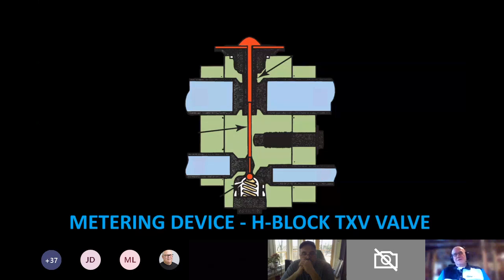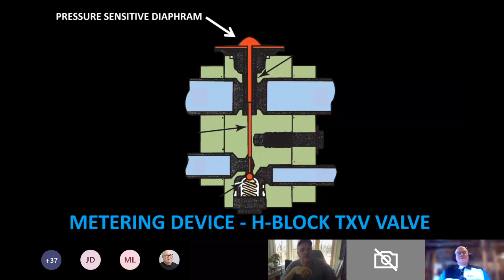We have a trainer with the TXV, but this one is the H block, and I've cut it away. I'll show you what's going on here. It is a metering device. It is designed to meter the flow of refrigerant into the evaporator. And so we have the same diaphragm that was on all TXVs is still there.